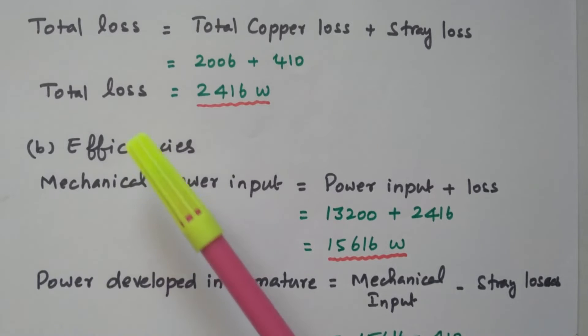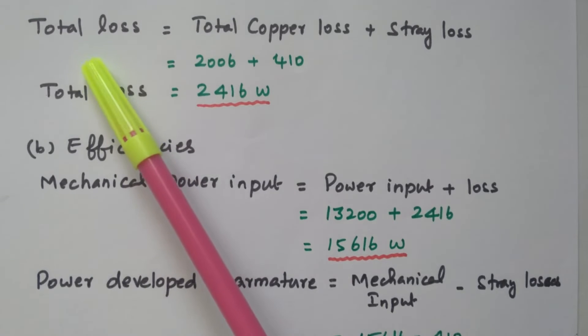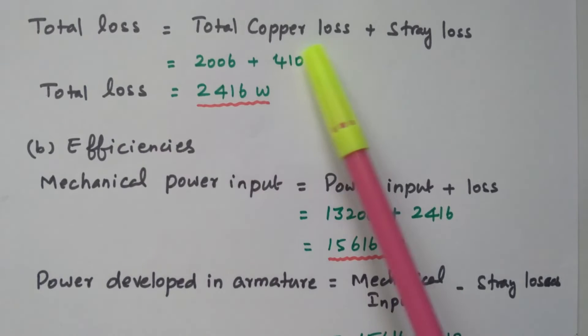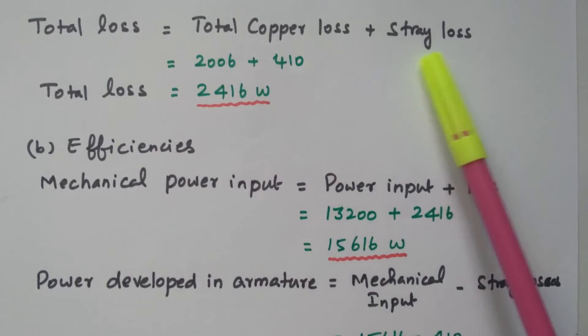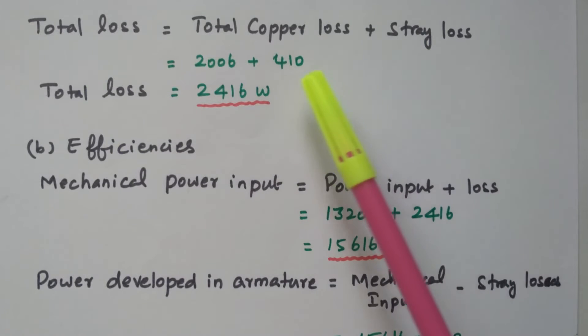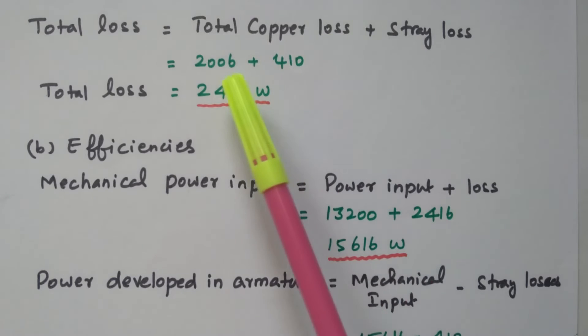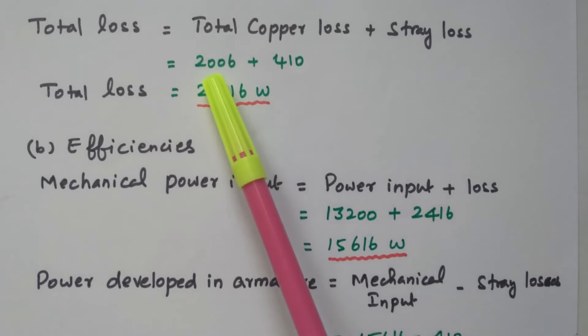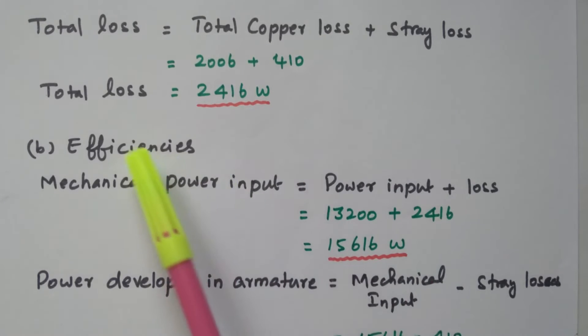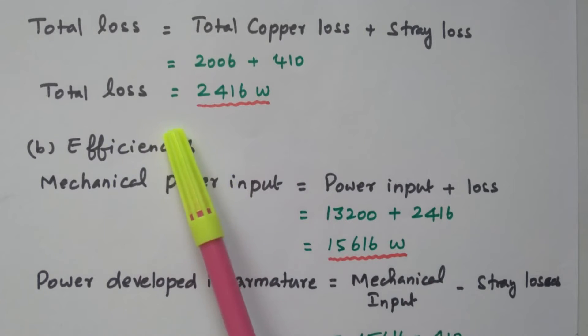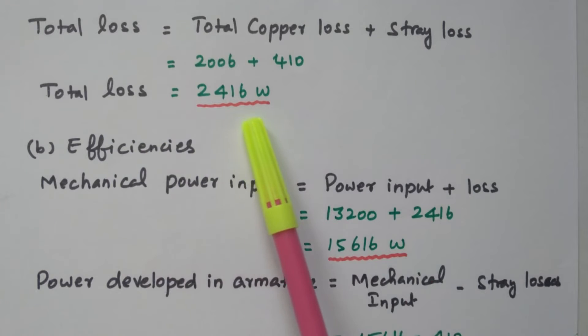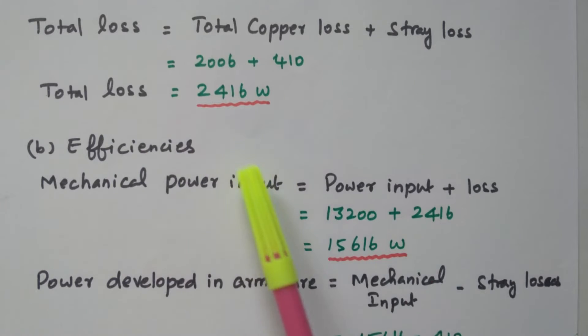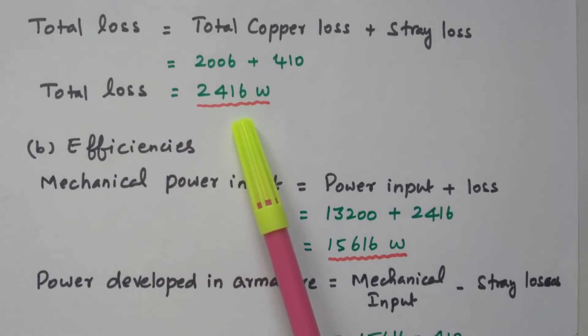Now we can calculate the total loss. Total loss = total copper loss + stray loss. The stray loss given in the problem is 410 watts and the total copper loss calculated is 2,006 watts. So the total loss is 2,416 watts.